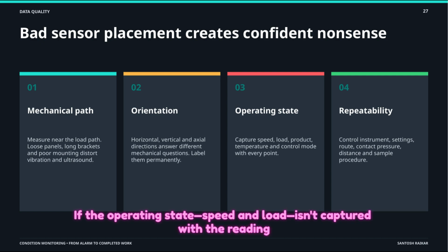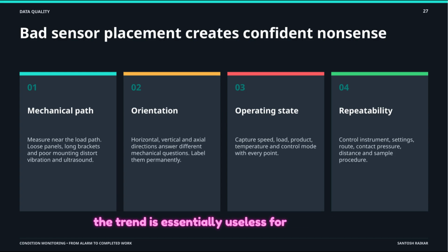If you have bad sensor placement, you're just generating confident nonsense. We must measure as close to the load path as possible and permanently label sensor locations. If the operating state, speed, and load isn't captured with the reading, the trend is essentially useless for comparison. Finally, we use evidence fusion. We don't need every technology to show a fault, but we do want them to tell a coherent physical story. When vibration shows a specific frequency and the oil analysis shows the corresponding wear metal, your confidence in the diagnosis skyrockets, making the work scope decision ready.